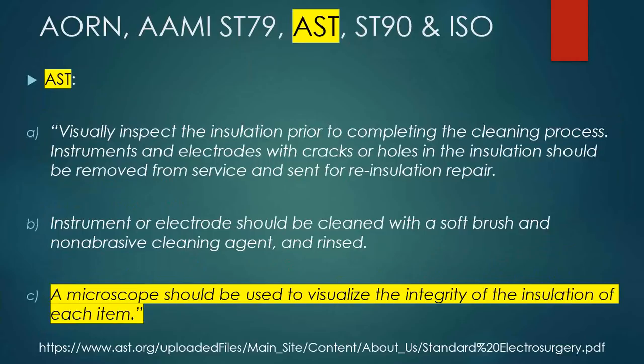First, visual inspection of the instrument prior to completing the cleaning process. Instruments and electrodes with cracks or holes in the insulation should be removed from service and sent for reinsulation repair. It's a good idea to clean instruments or electrodes with a soft, bristled, non-abrasive cleaning agent, because other things will damage the insulation we're trying so hard to protect.